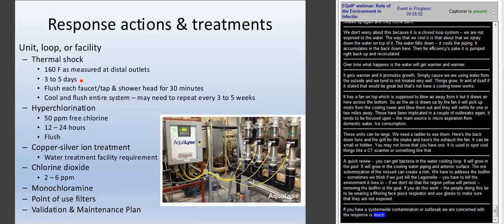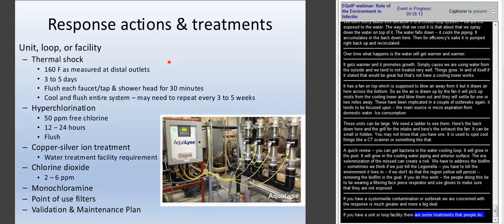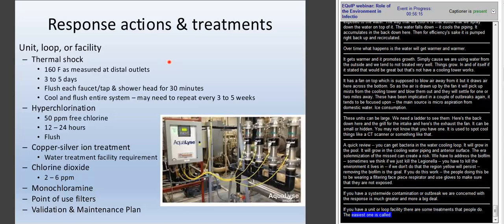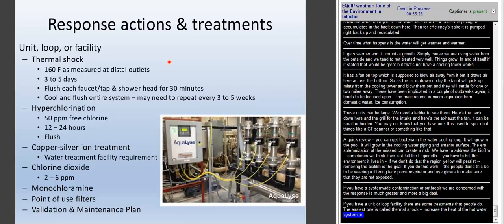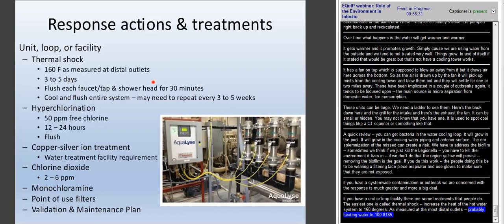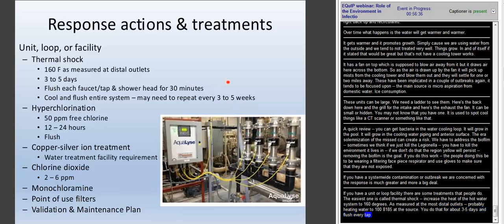I'll keep it simple. If you have a unit, a loop, or a facility issue, there are a number of treatments people do, and the easiest one is called thermal shock, where you increase the heat of the hot water system to 160 degrees as measured at the most distal outlet. So you're probably heating the water to 180, 185 at the source, and you do that for about 3 to 5 days, flushing every single tap, shower head, and distal outlet for 30 minutes to make sure you've killed the biofilm and the Legionella throughout.